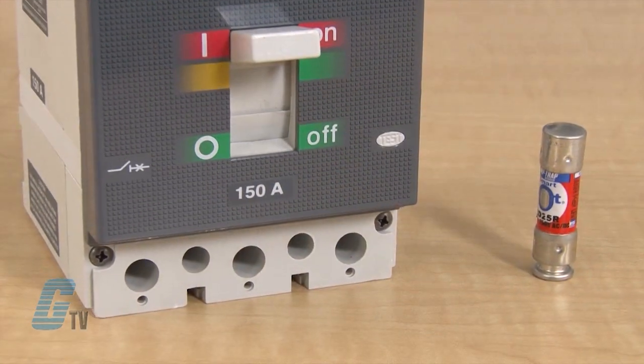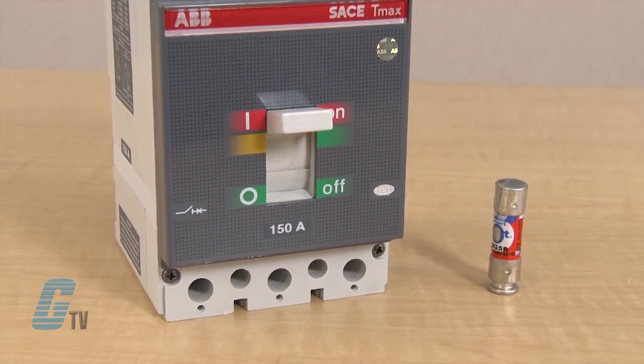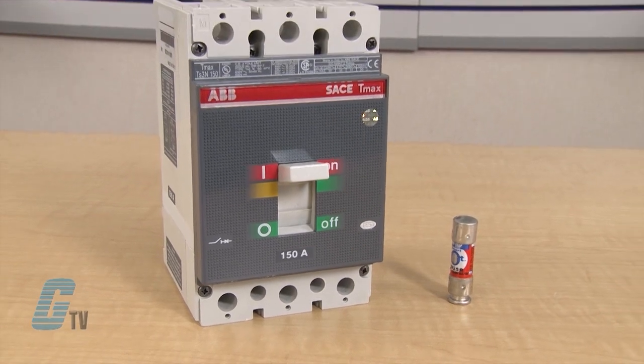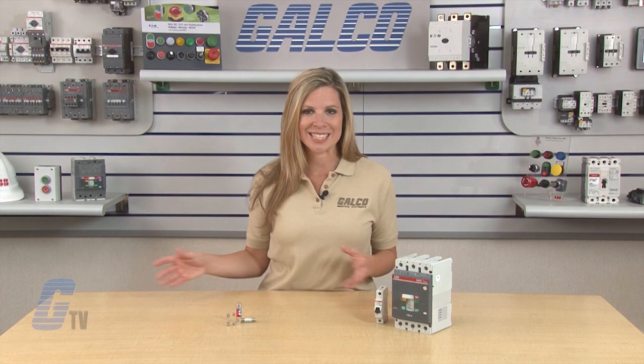Options for remote tripping or auxiliary circuits are also readily available for most types of breakers. A possible disadvantage to circuit breakers is that let-through currents may be higher compared to a fuse. Some fuse designs provide faster response times to fault currents than circuit breakers are able to achieve.